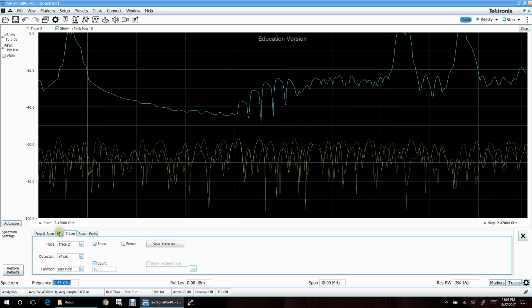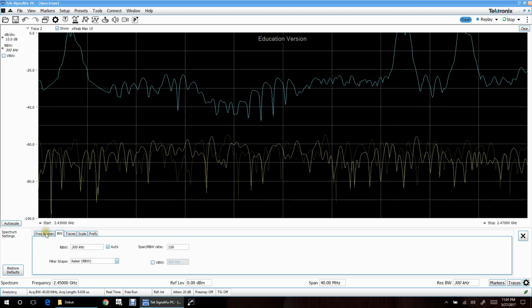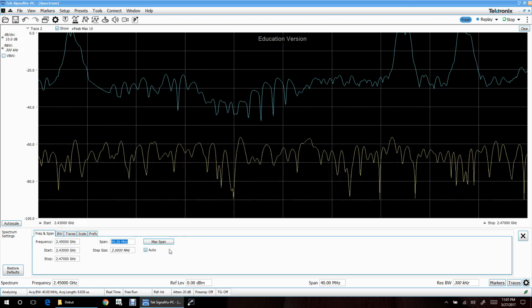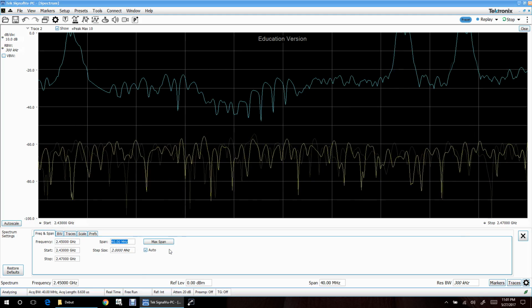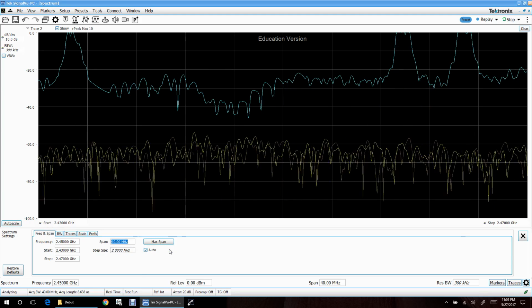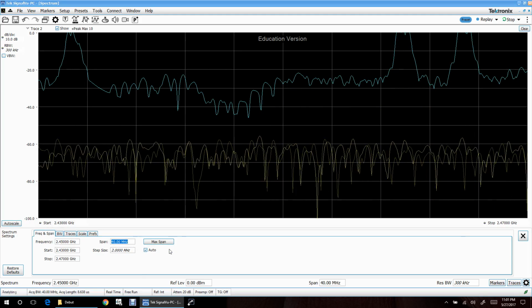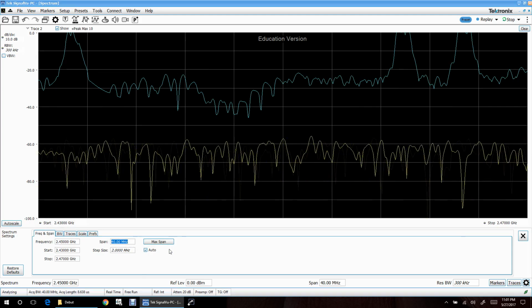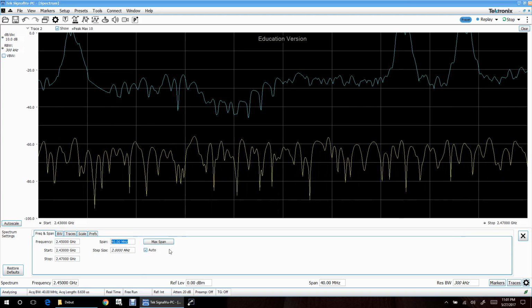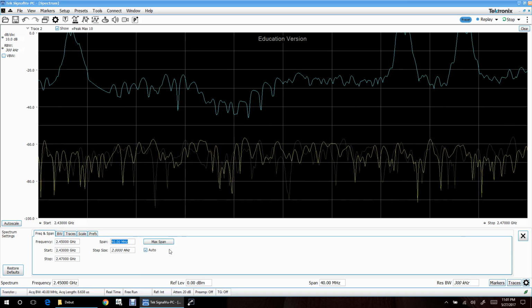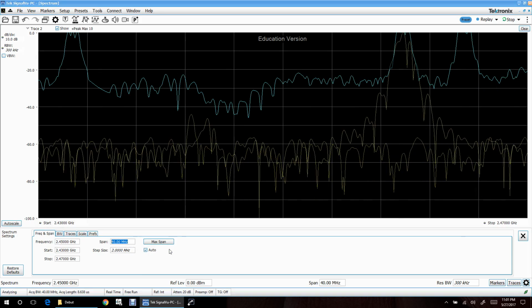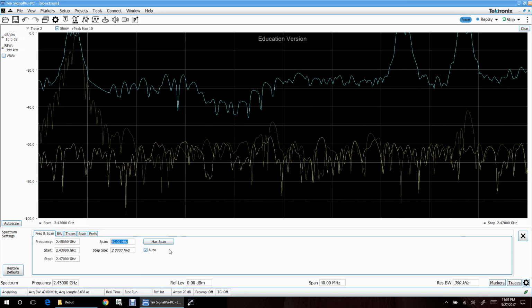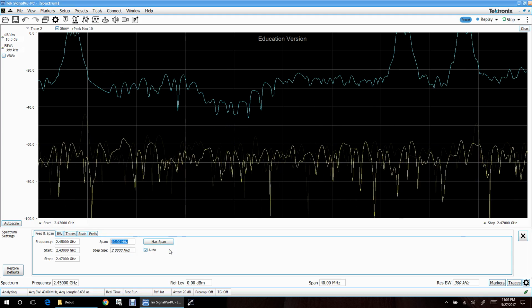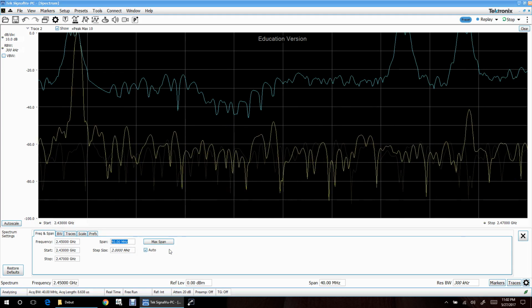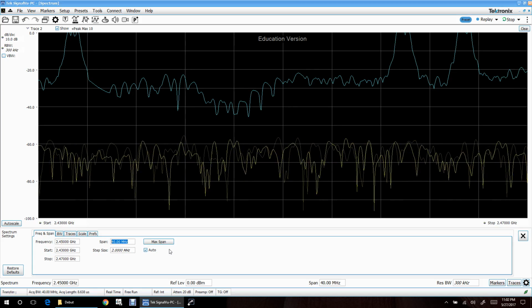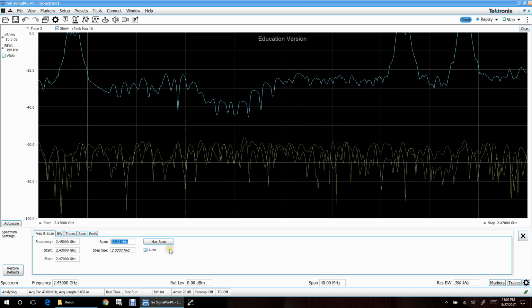Now it would be great if this had, instead of a 40 megahertz bandwidth, let's say 110 megahertz bandwidth. But the challenge with that is that on a USB instrument like this one, if you were to increase the span from 40 to 110, aside from all the hardware difficulties from the RF portion itself, you're going to have to send a lot more data to the PC. So maybe next generations of these instruments, when there is USB-C and Thunderbolt and so on, they would be able to have higher analysis bandwidth. But 40 megahertz is plenty, and there's a lot you can do with just 40 megahertz, as you will see.